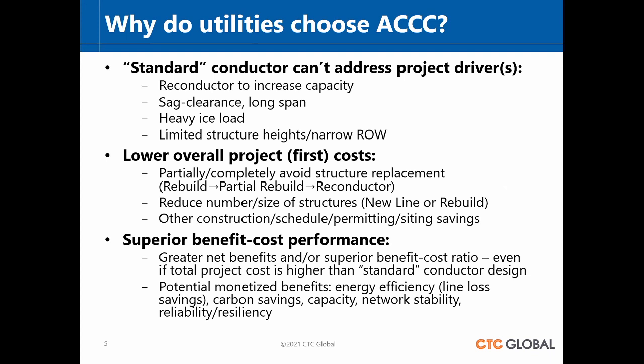We also see it when there's a lower first cost. Just the initial cost is lower. That's the case in one of these unique applications where you can actually reconductor wire for wire on the existing structure. That's unique because of the weight and the size of aluminum that you have versus what you're taking down. It also means if you need that capacity, that's the least expensive way to get it. You don't have to rebuild the towers. That's a lower first cost, and we see some utilities move to this for that application.